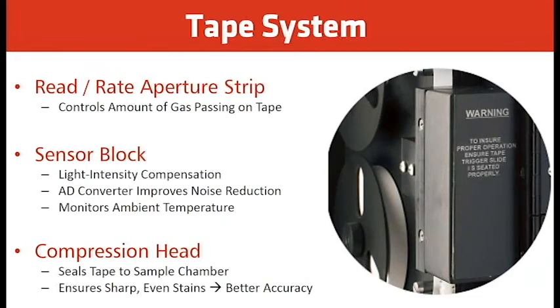Inside the sample chamber, we install what's called a read/rate aperture strip, which controls the amount of gas passing onto the tape. The higher the concentration, the smaller the opening on the aperture strip to allow the gas to stain the tape. The lower the concentration, the bigger the slot on the aperture strip to allow more gas to hit the tape.